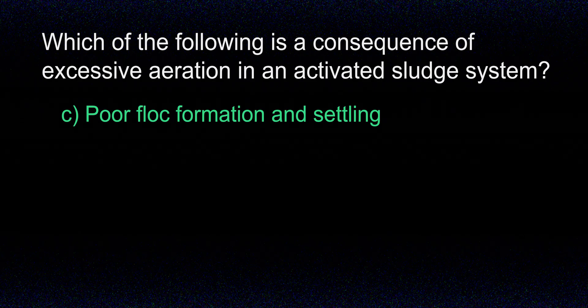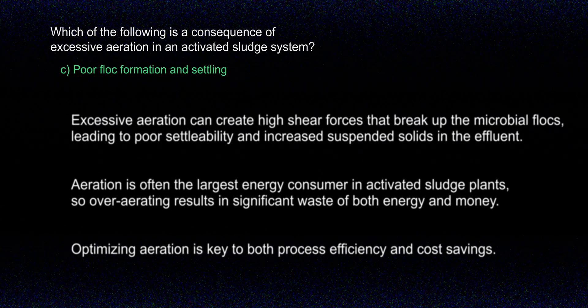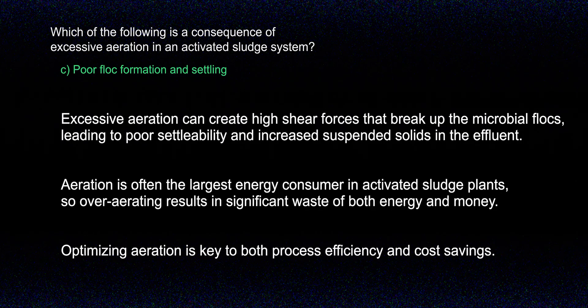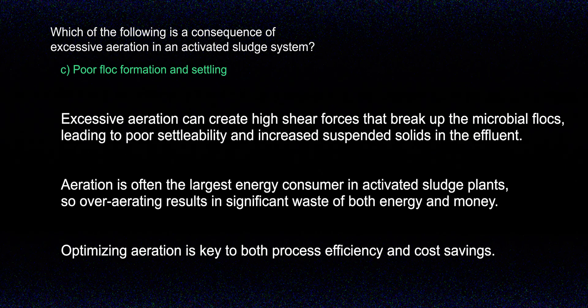The answer is C, poor floc formation and settling. Excessive aeration creates too much turbulence within the aeration basin, causing floc particles to break apart. Flock particles are clusters of bacteria and organic matter essential for proper settling and treatment. When they become too small or too few, they lose the ability to settle effectively in the secondary clarifier, leading to poor settling performance and higher suspended solids in the effluent. Additionally, aeration is typically the most energy-intensive process at an activated sludge plant, so running it beyond what's necessary also results in unnecessary energy consumption and higher operational costs.